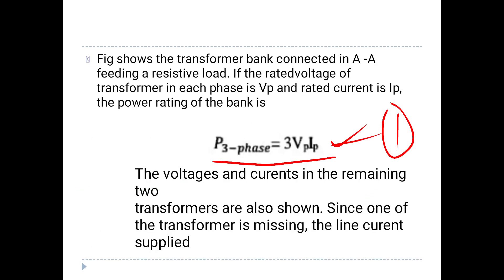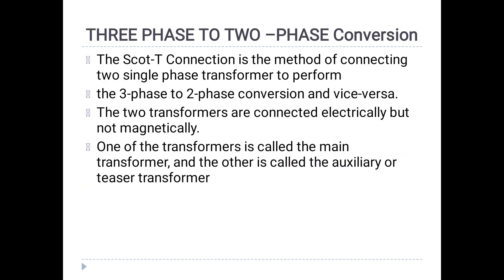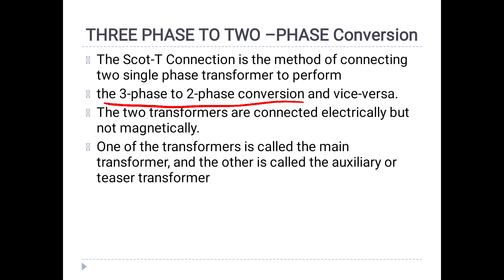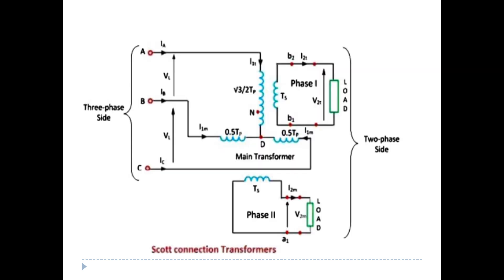Now, in this situation, we have a VV connection and a 3-phase to 2-phase conversion. This is the method of connecting two single-phase transformers to perform the 3-phase to 2-phase conversion, or vice versa — the Scott-T connection. We use two single-phase identical transformers: the first is the main transformer, and the second is the auxiliary or teaser transformer.